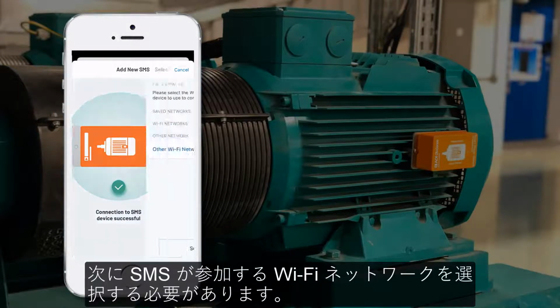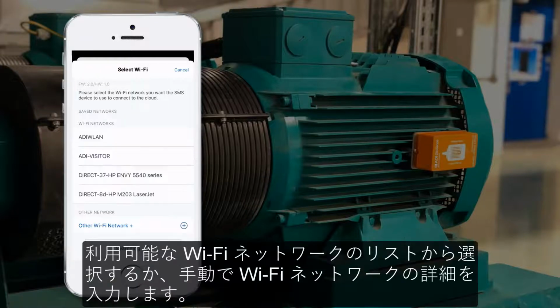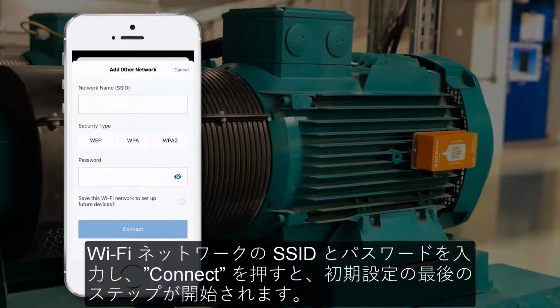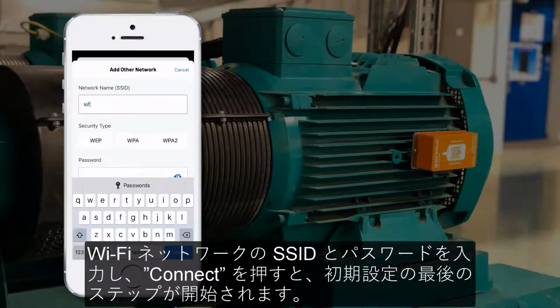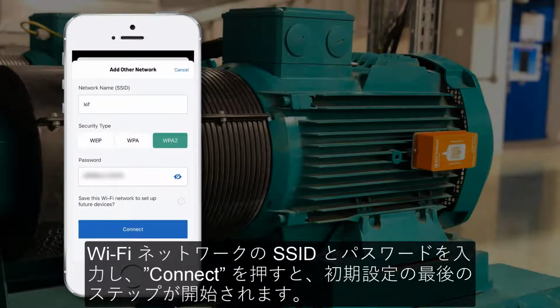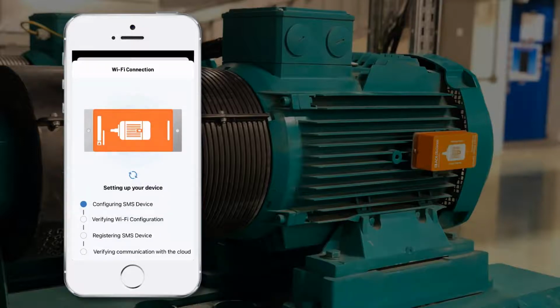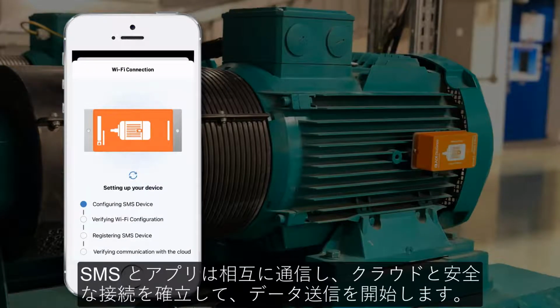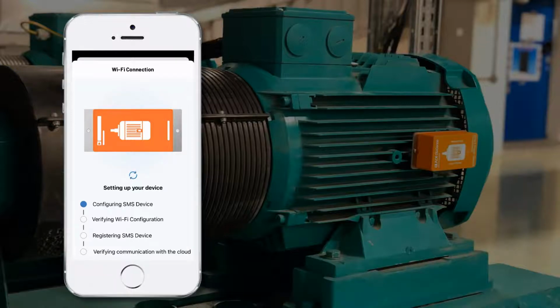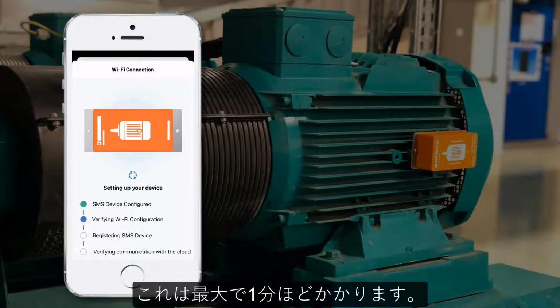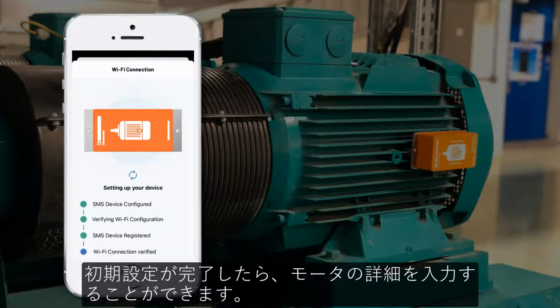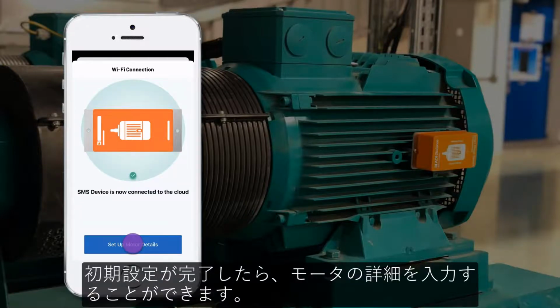Next, you need to select the Wi-Fi network the SMS will join. You can select it from the available Wi-Fi networks list, or manually enter in the details of the Wi-Fi network. Enter the SSID and the password for the Wi-Fi network and press Connect to start the final step in commissioning. The SMS and app will now communicate with one another and with the cloud to securely establish a connection so that the SMS can start sending data. This can take up to a minute. Once the commissioning is complete, you can start entering in the motor details.